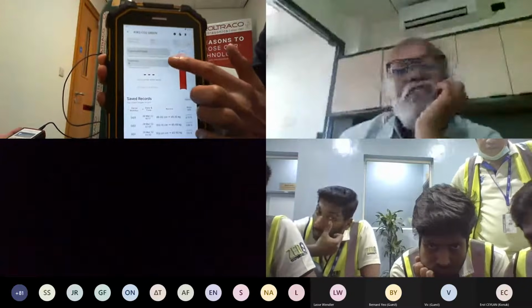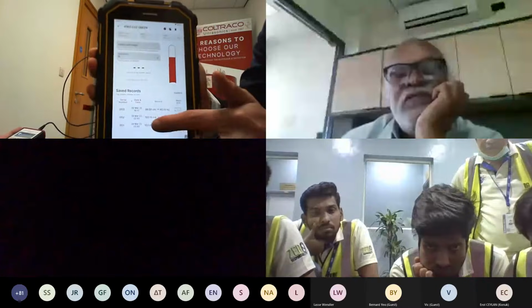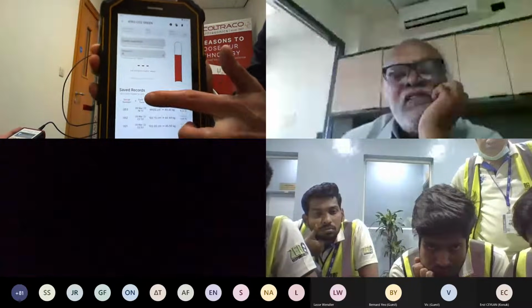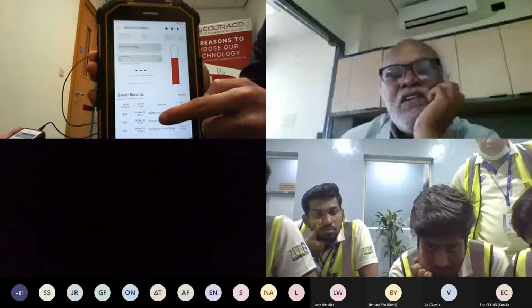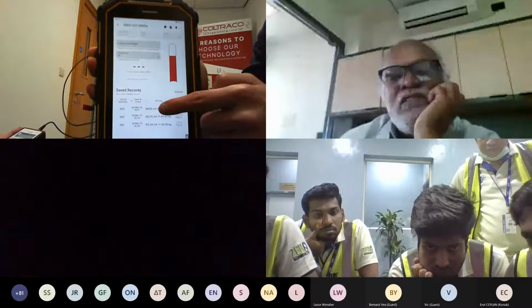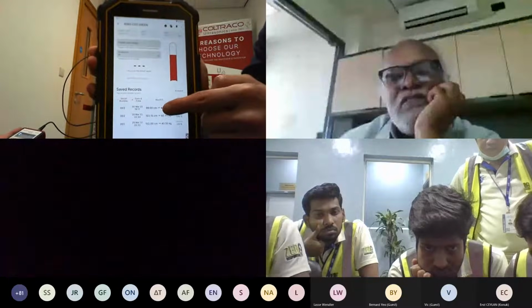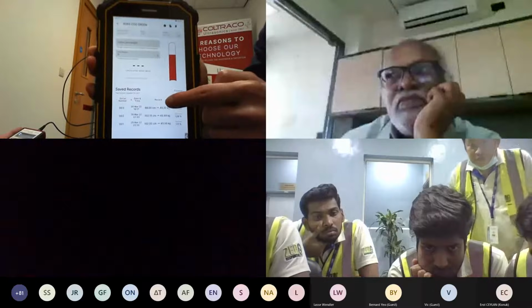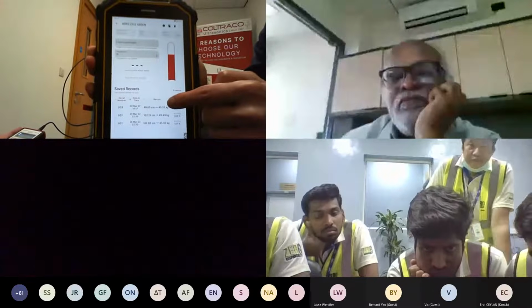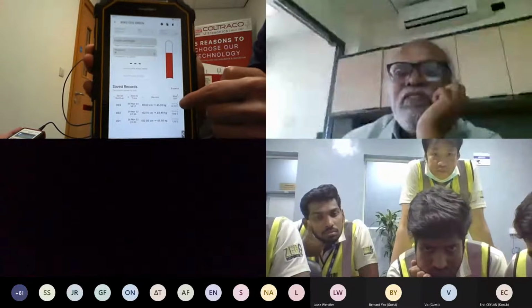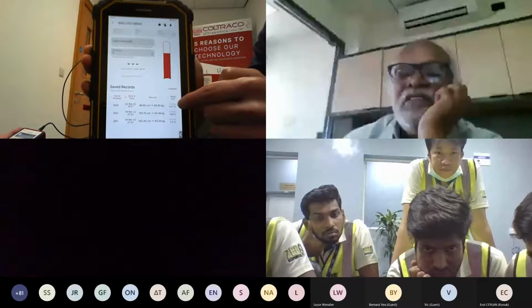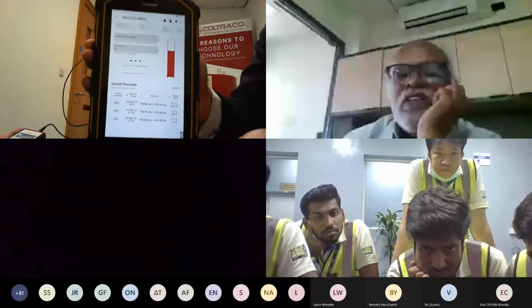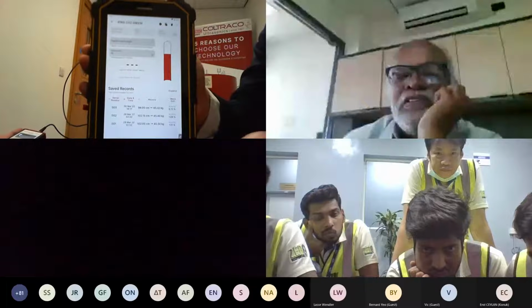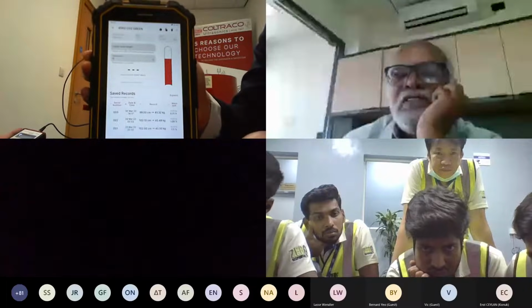This will bring that record down to the database below. The serial number that I've just entered, you will see is 003. Today is the 30th of March. And the liquid level found was 99 centimeters and it's converted to 45 kg. And the percentage difference is 0.71%. So this is within the 5% or 10% tolerance as required by the regulations.